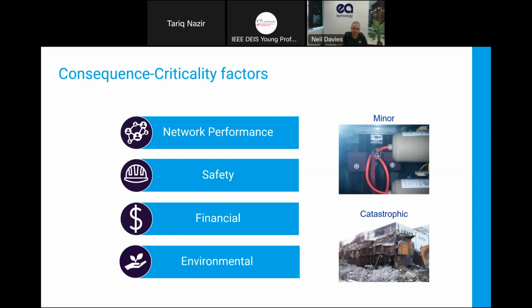And the consequences and criticality factors that we deal with on any network are all to do with network performance. So I've got an outage, downtime, or SAIDIs or SAIFIs on the electricity network. There's always a safety aspect, of course. If you've got a catastrophic failure, as we can see in the bottom right there, if you're in the vicinity of that when that happens, then there's a significant safety issue. So we need to be dealing with that. There's definitely a significant financial issue if you've ended up with a substation that looks like the bottom right graphic. The financial issue of letting things fail is that it's always a more expensive exercise to fix after failure than it is to prevent that failure by intervention. And of course, there are environmental aspects of criticality if we're releasing oil into the environment or burning oil and gases, for example.